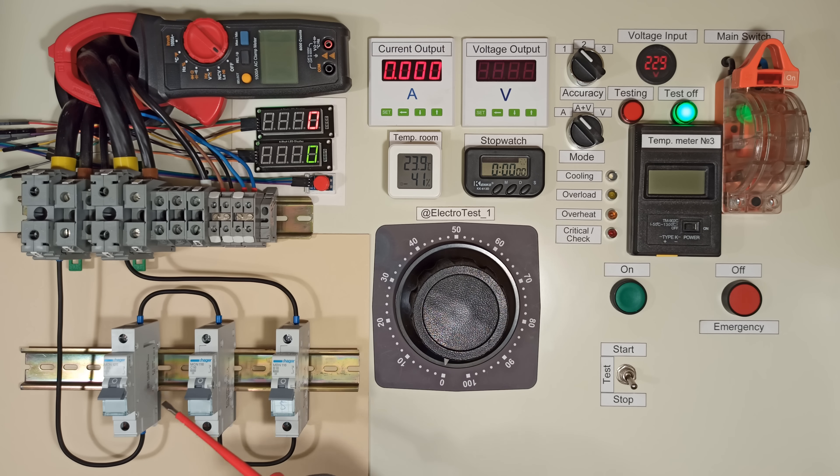I tested the 16A breakers separately in detail. Now we'll pass current at the same time through all three breakers and see how they trip. I'm especially curious when the main breaker will trip. This is a selectivity test. Let's begin.